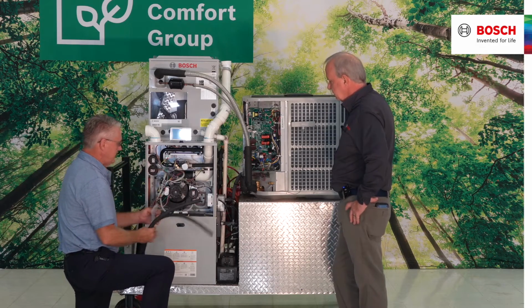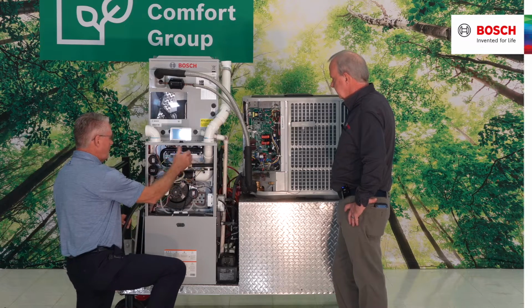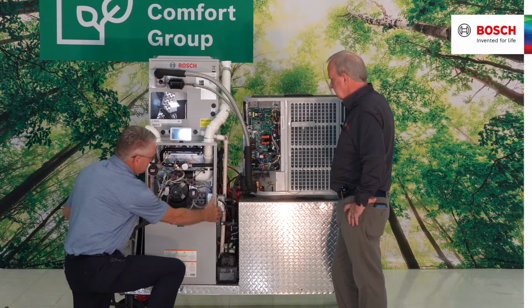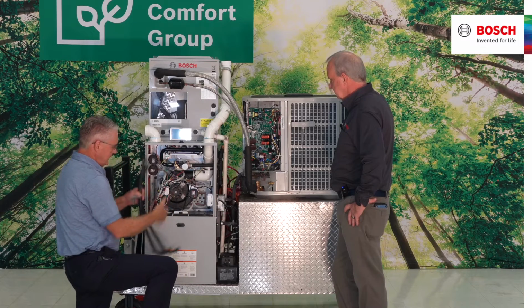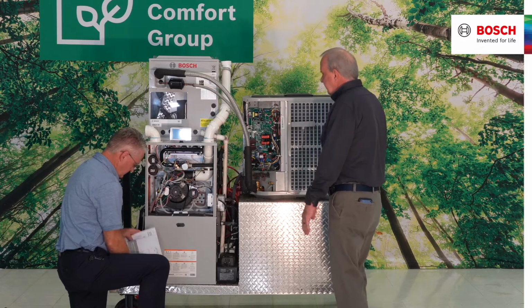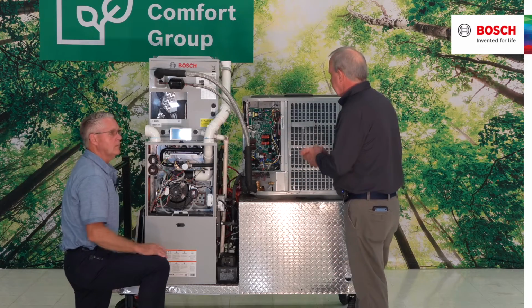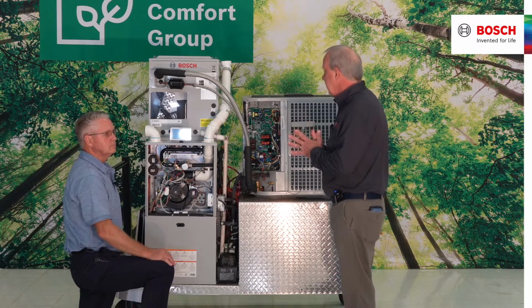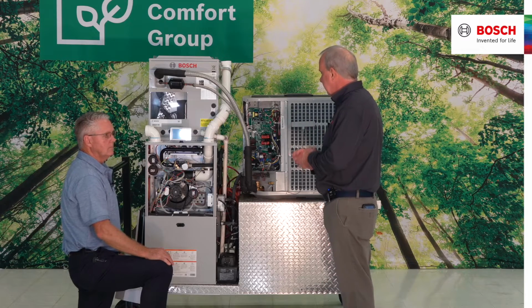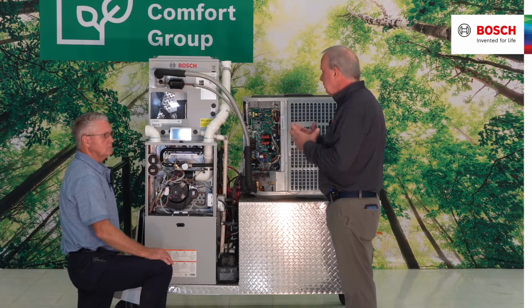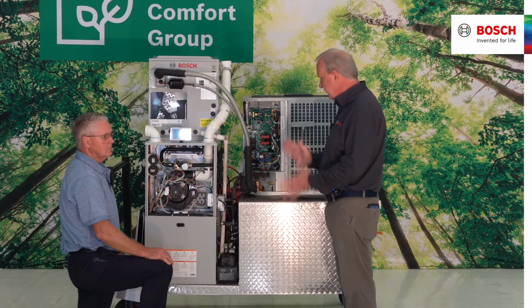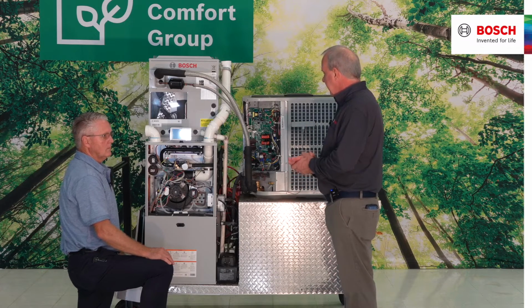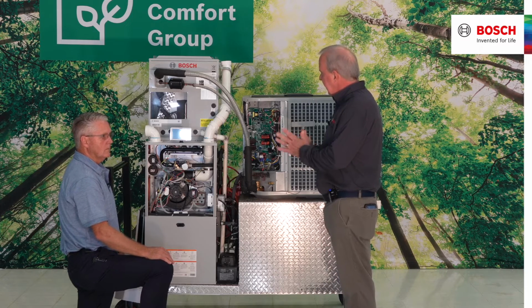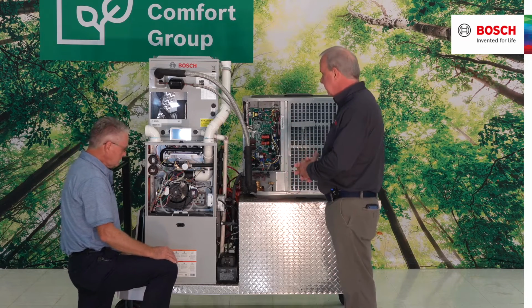So again, all of the necessary items to take the water away from the secondary heat exchanger back down into the collection plate is included in this unit. With this being a 90% condensing furnace and producing so much condensation during the heating cycle, whether it's low fire or high fire, it's critical that we get all of this moisture, all this condensation, out of this furnace. Does the installation explain having a little bit of fall in the furnace to get all of that water, moisture, condensation out of there?